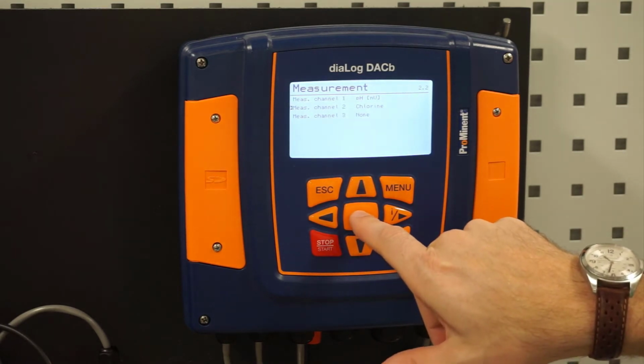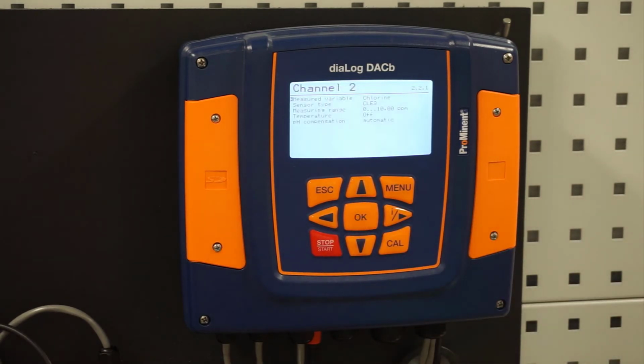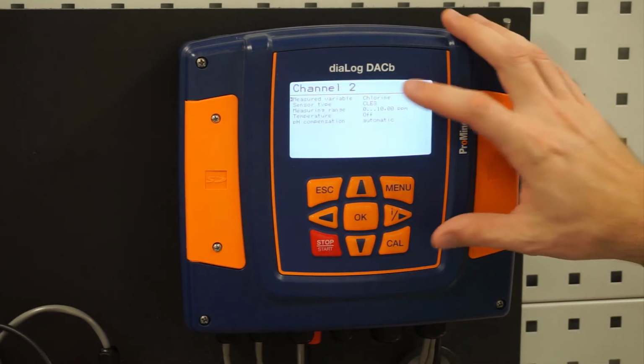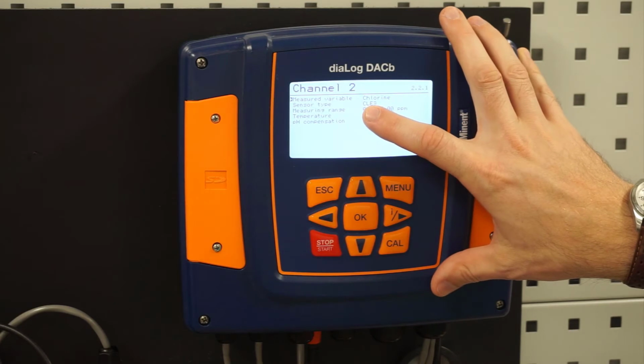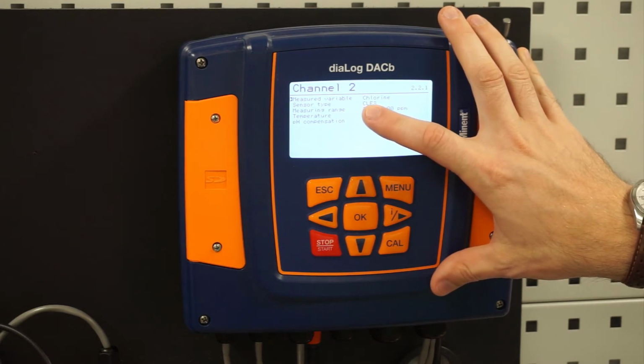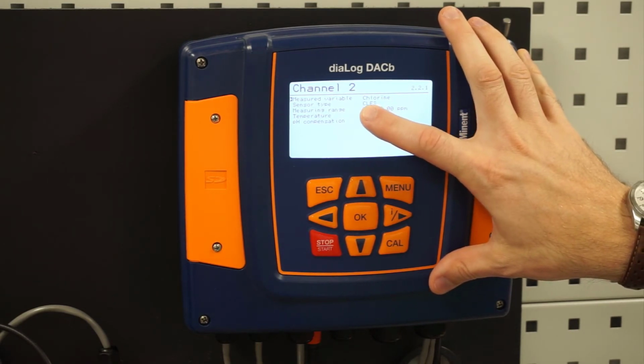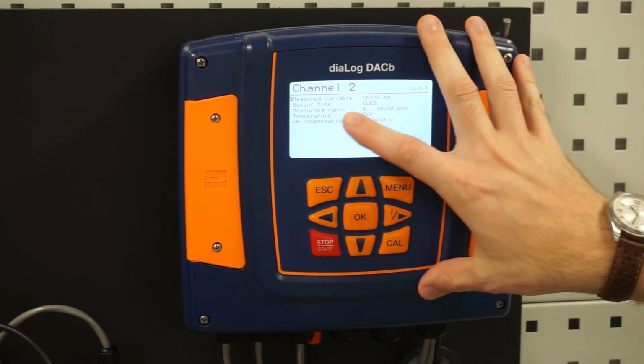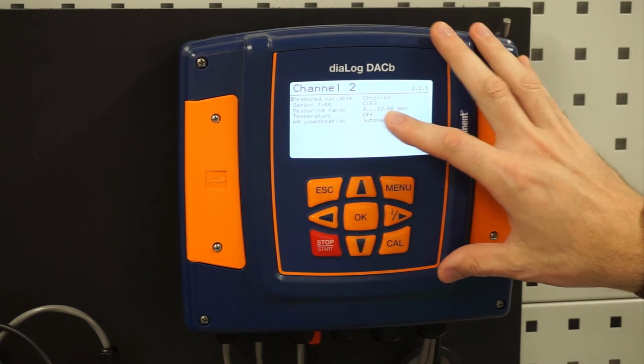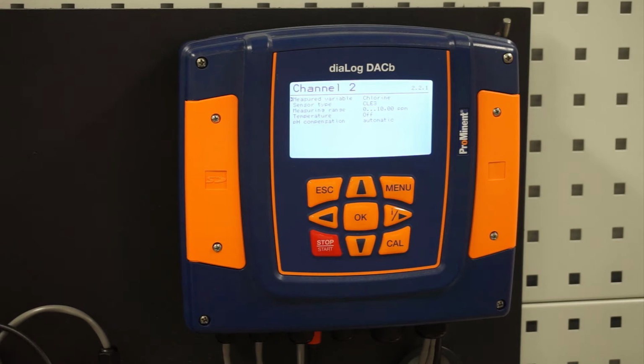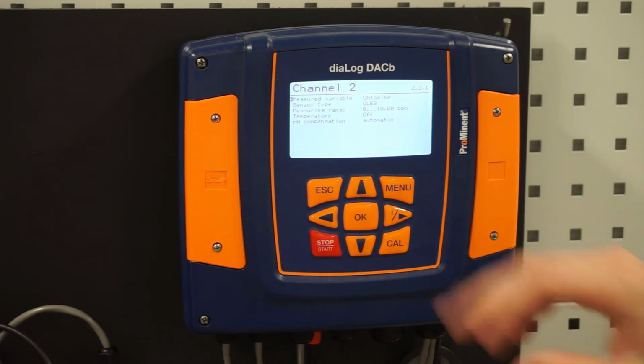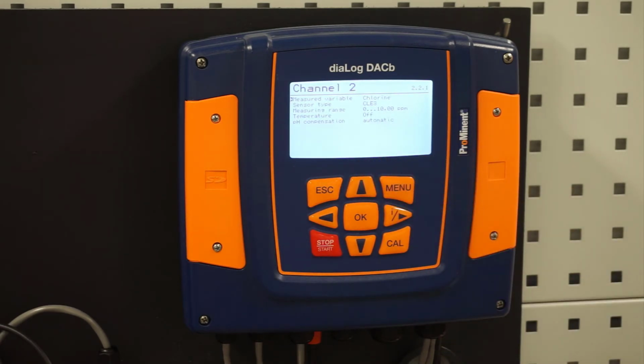Next is my channel 2, which is free chlorine. This will be set up, but it's good to verify. On your sensor that you have installed, it will tell you what the sensor type is. So my sensor is a CLE3, and my measuring range is 0 to 10 ppm. All right, you will get those numbers right off of the sensor.